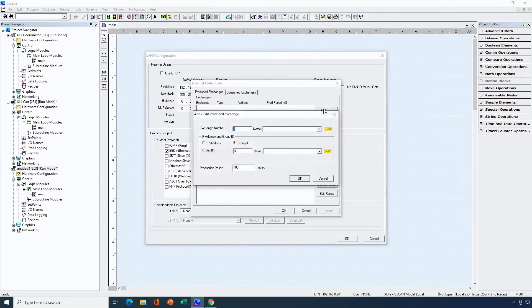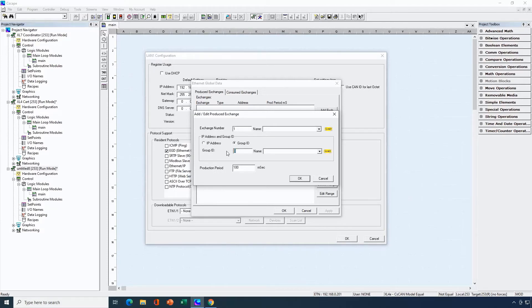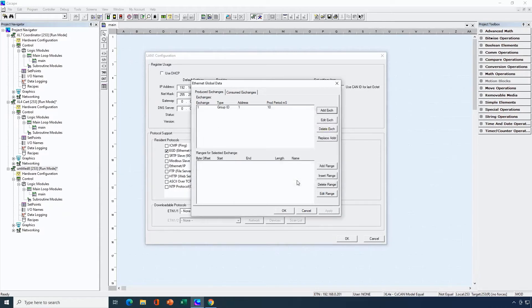We'll start by configuring our exchanges. Let's add an exchange — remember, think of it as an envelope. The exchange must have a number between 1 and about 16,000. I'll just set it to 1. Then I need to decide: am I sending it to an IP address of a single node or am I sending it to a group? Let's say I'm sending it to a group. I have to assign a group ID between 1 and 32, and I'll set that to 1. Then I'll input how often I want to produce the data — I'll send that out every 10 milliseconds. So I've configured the exchange envelope but now I need to put data inside of it.